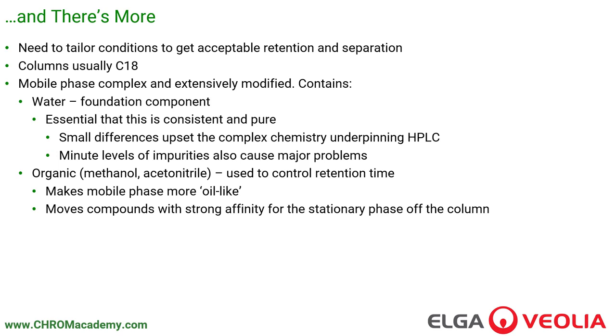There's a lot more to it than that. We really need to tailor the conditions to get acceptable retention and separation. Although the columns are usually C18, the mobile phase is an extremely complex mixture and usually extensively modified. It contains water, which is absolutely the foundation component. We must retain a mobile phase that has the opposite polarity to the C18 oil-like stationary phase. It's essential that any water we use is consistent and very pure. Small differences in the water upset the complex chemistry underpinning HPLC, and minute levels of impurities can cause major problems with the stability, precision, and accuracy of the HPLC process.